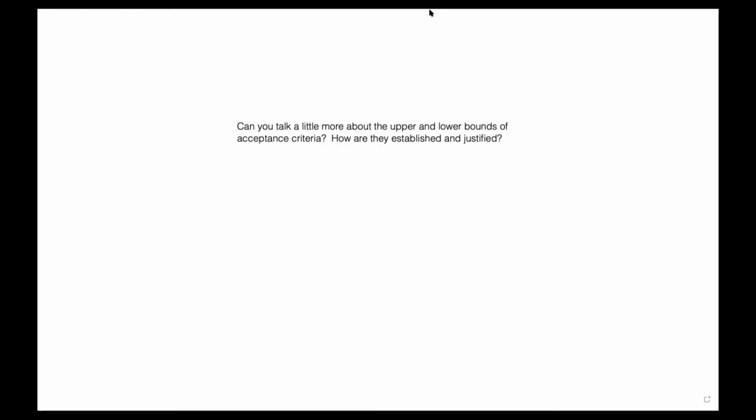Let's just say I'm going to use a cardiac stent, for example. Some of the safety and performance objectives might be rates of MACE events, stent restenosis rate, and rates of cardiac death at 6 months or 1 year. These are very specific safety and performance objectives, and whatever those are for our subject device, we're going to be looking for results in the competitors for those same objectives.